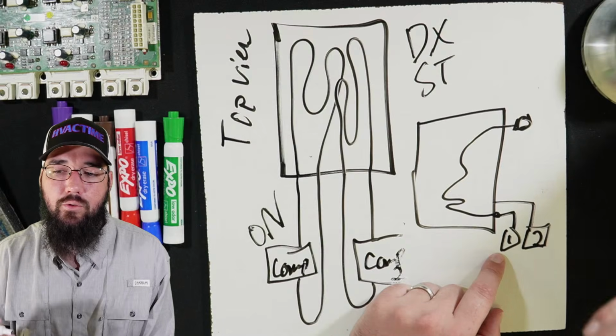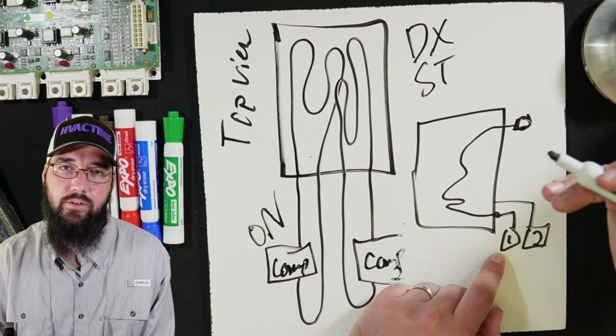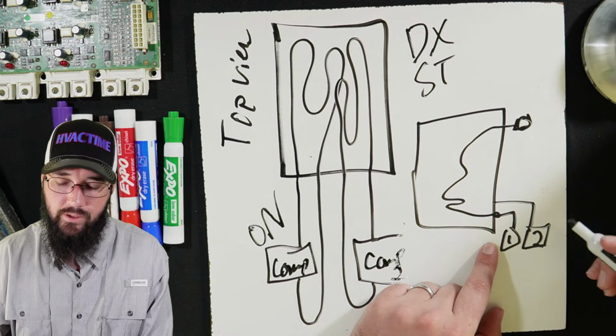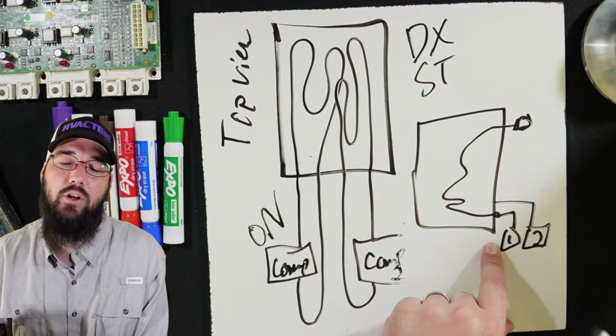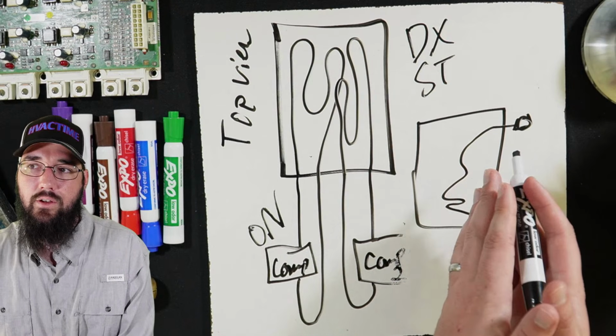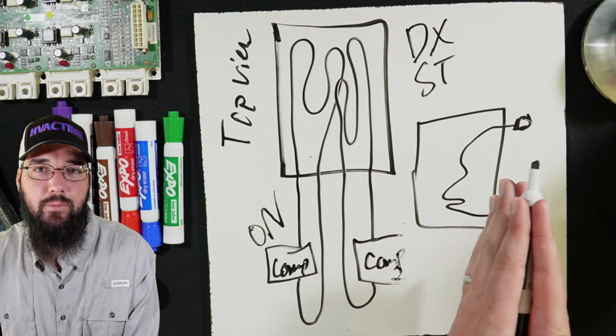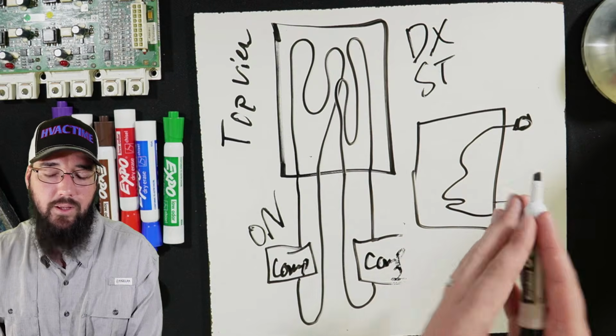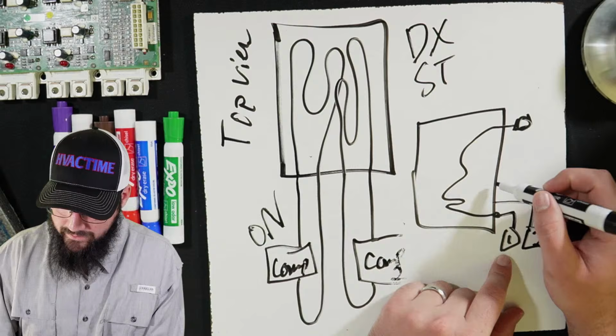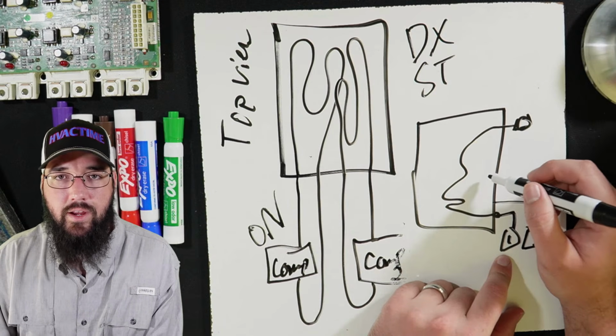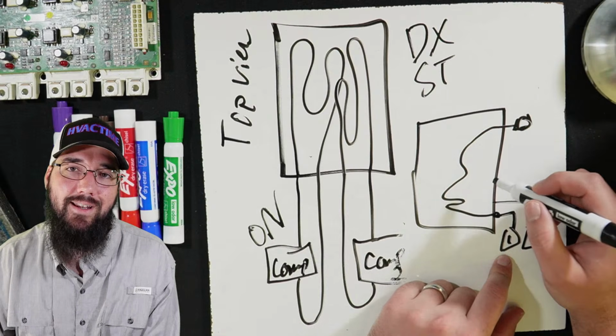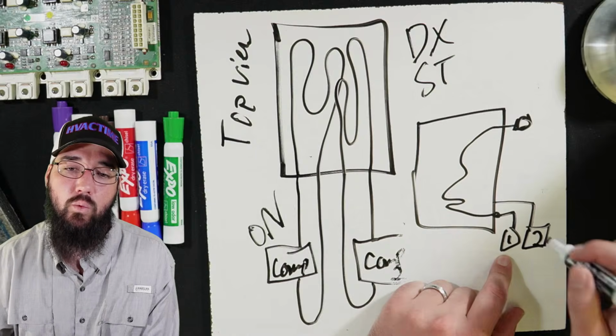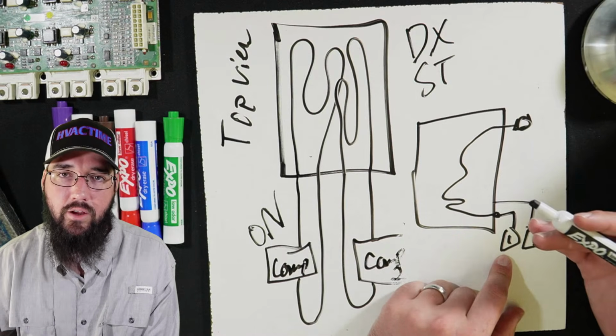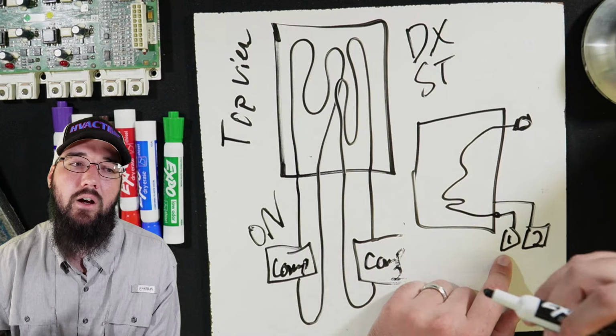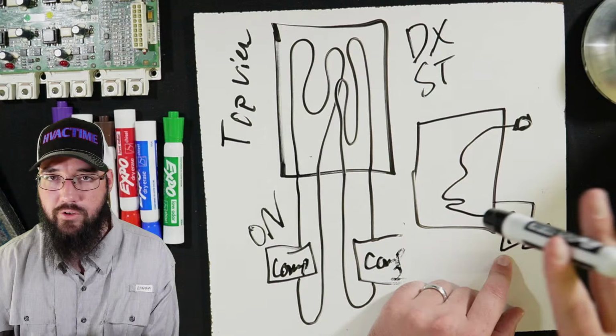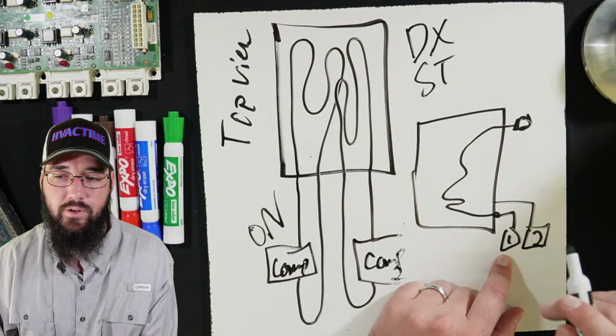Even if you're hitting set point, let's say you had a low load on this RTU and you were hitting set point, because we only have one circuit on this interlaced, oh, maybe that's the term, interlaced, I think that's the right term, on this interlaced coil, because only one circuit is activated, the entire heat load of that coil is being taken in by one. That means there is a lot of heat for just the one circuit. So you're going to see higher saturation values, even though we may be achieving our supply air temperature set point in a low load condition, for example, or a derated condition.